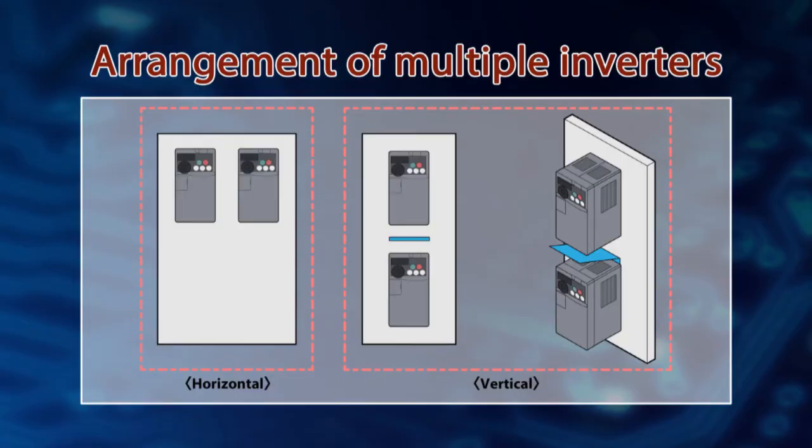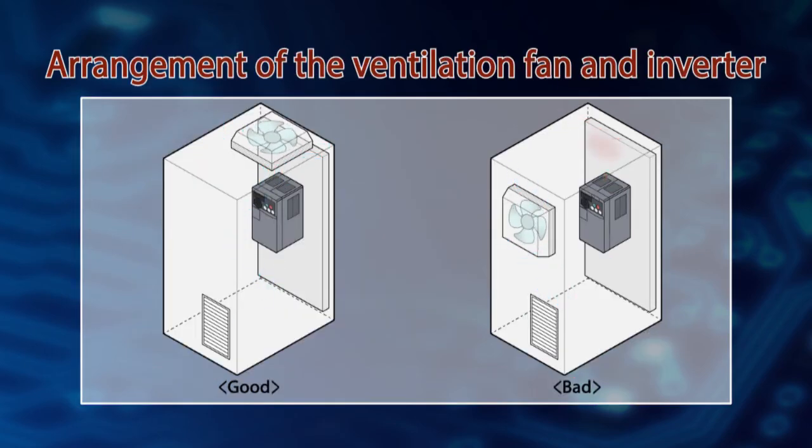Now let's check how to install multiple inverters onto the operation cabinet. When installing multiple inverters in the same enclosure, place them horizontally as shown in the left figure. When placing them vertically, provide air guides between inverters to prevent possible failures due to the temperature rise inside the upper-row inverter from the heat of the lower-row inverter, as shown in the right figure. In addition, provide ventilating openings or enlarge the enclosure to keep the surrounding air temperature of the inverter lower than the permissible temperature.